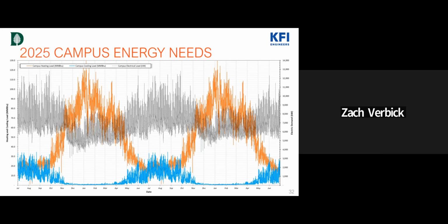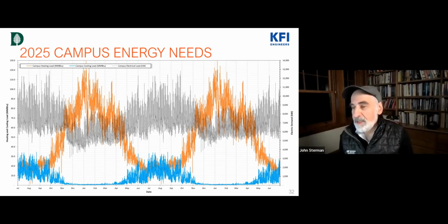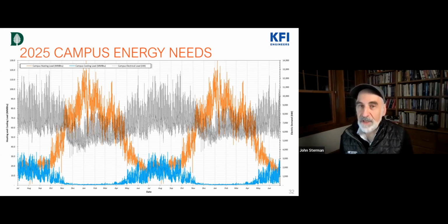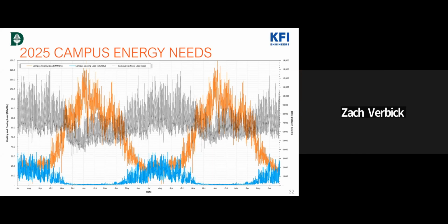I think the goal ought to be to avoid needing that if at all possible, so we can have a zero combustion system. But think about the boundary, not just around the whole campus, but including where the utility is going to be getting the juice for the coldest days to feed an electric system. If they're turning on a dirty plant to meet that peak load on January 20th when it's 10 below zero, it's complicated, but it won't be very many hours per year. And the avoided capital cost of not needing a biofuel backup is really, really big. So it's a really good point.